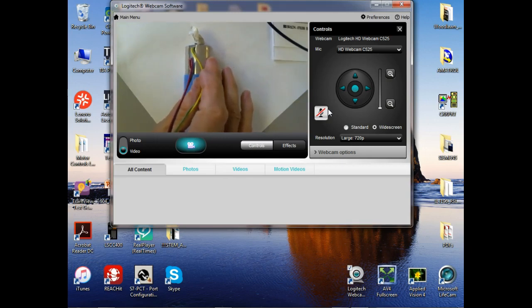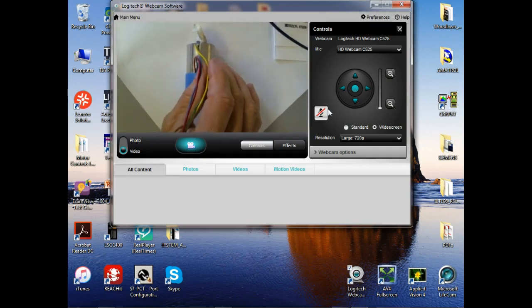So most of your DC motors, and if you're troubleshooting, of course, we're going to have to go over those. And we went over those in motor controls too. Your DC motors that we have the best control over, we can not only control the armature voltage, we can also control the field voltage, right? So if I increase the field voltage, the motor gets more torque, but it slows down. If we decrease the field voltage, we get less torque, but the motor speeds up, which is kind of strange, unless you understand the motor.